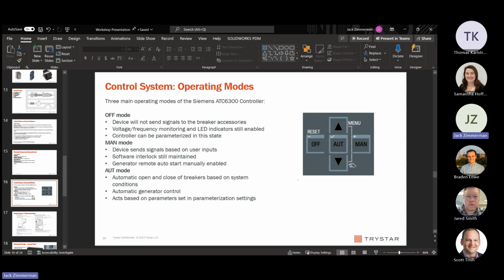In off mode, the device will not send a signal to the breaker accessories. It'll meter the power, it'll sound alarms, and you can turn alarms on and off in this state, but it will not change the breaker state no matter what. This is the only state that the controller can be parameterized in.